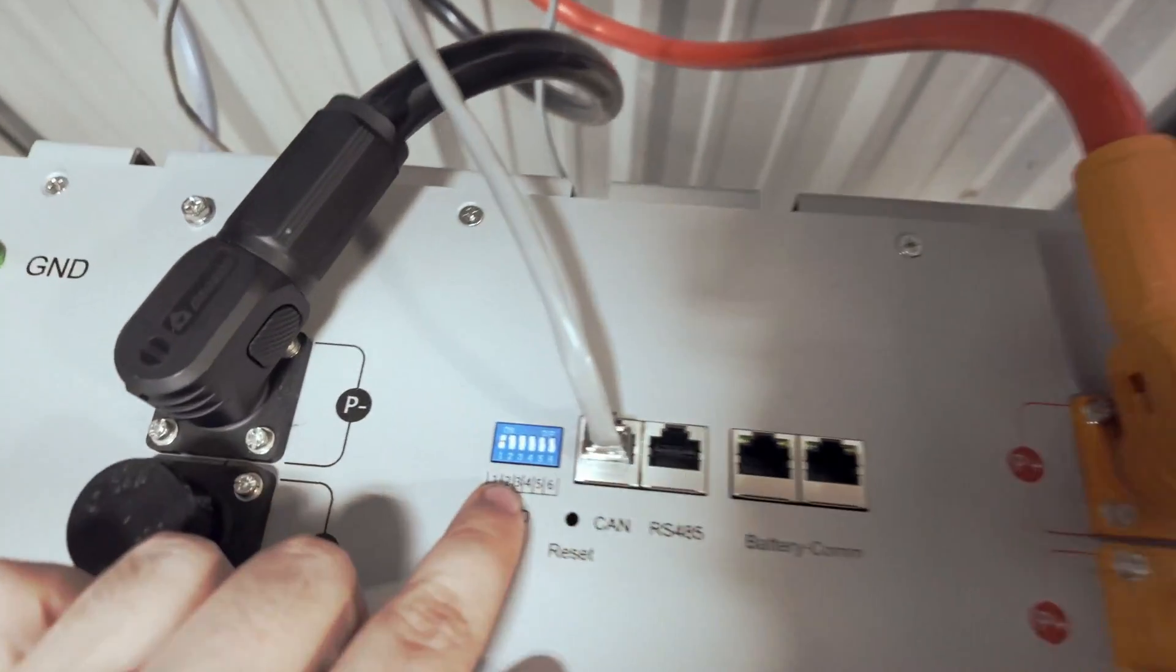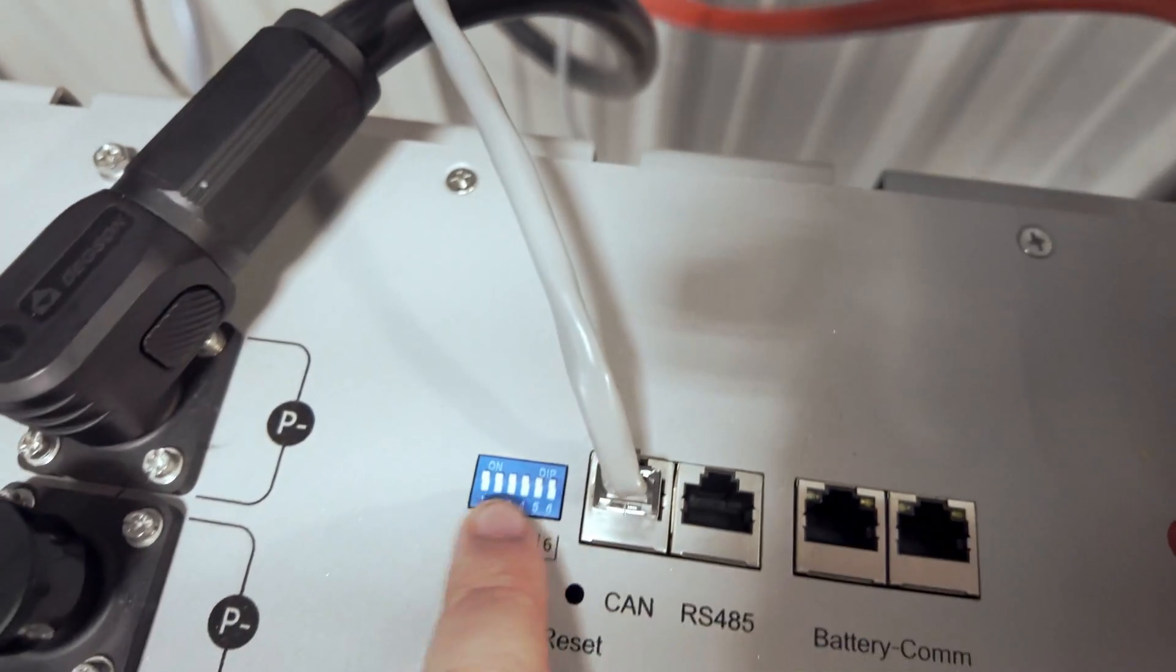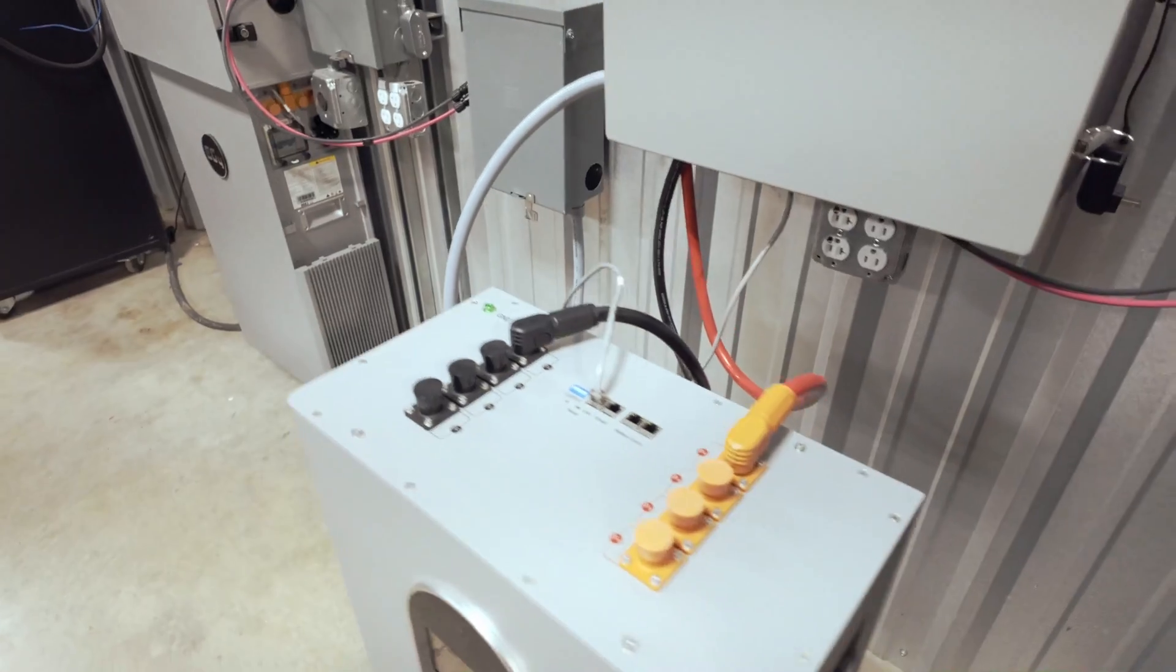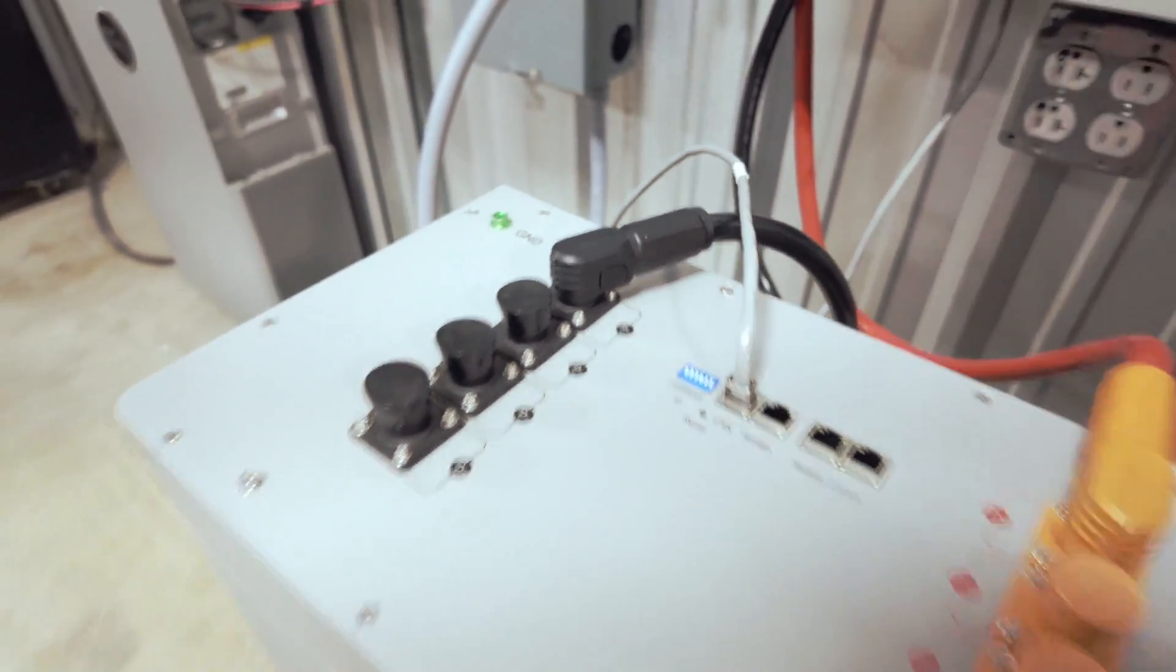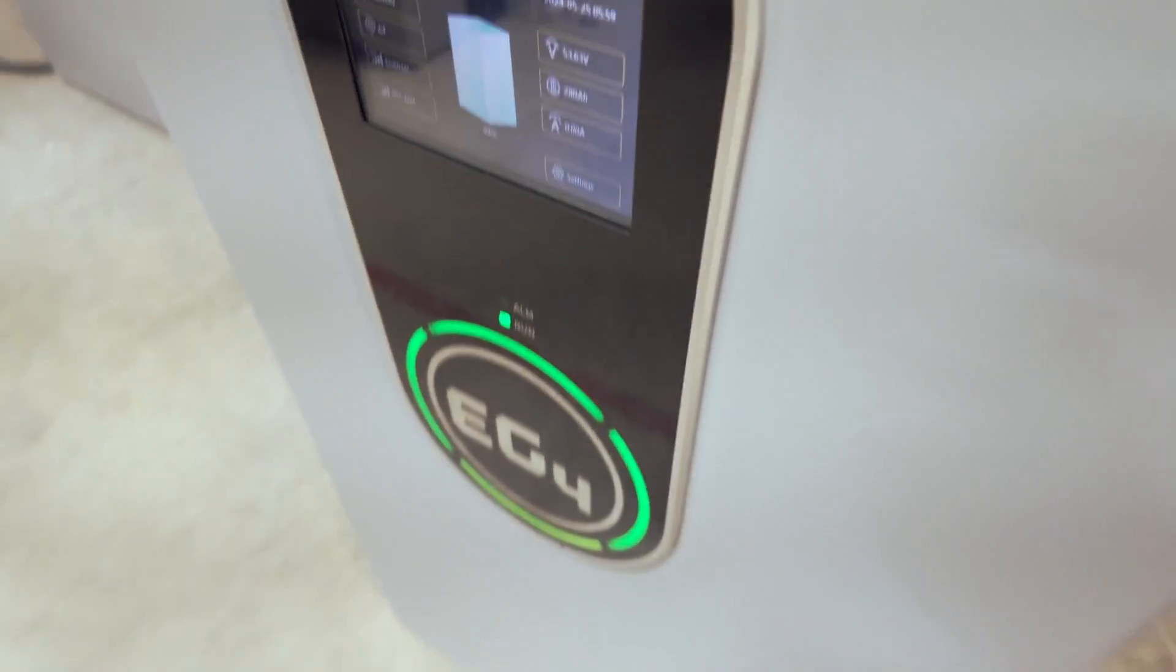Now for the dip switches, we will want to set all of them up. So all of them up like that. We'll go ahead and close this before we turn anything on to be safe. Don't want to get shocked. And now we will go ahead and turn our battery on. Again, you'll want your dip switches to be in the all up position on your wall mount or EG4 battery.